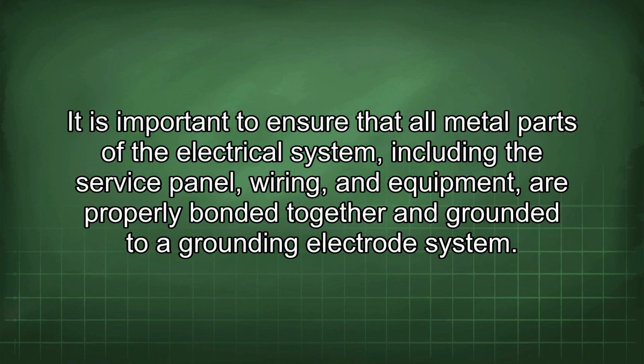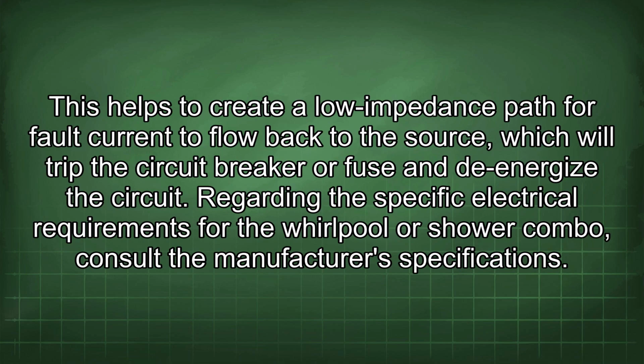It is important to ensure that all metal parts of the electrical system, including the service panel, wiring, and equipment, are properly bonded together and grounded to a grounding electrode system. This helps to create a low impedance path for fault current to flow back to the source, which will trip the circuit breaker or fuse and de-energize the circuit.